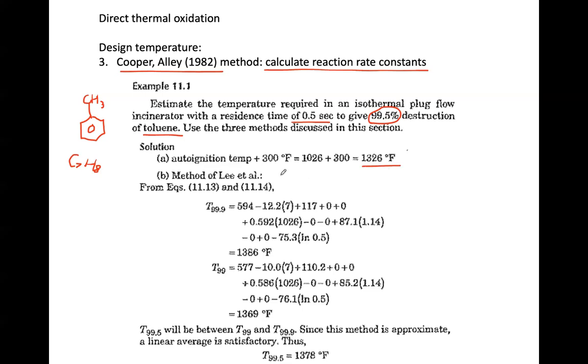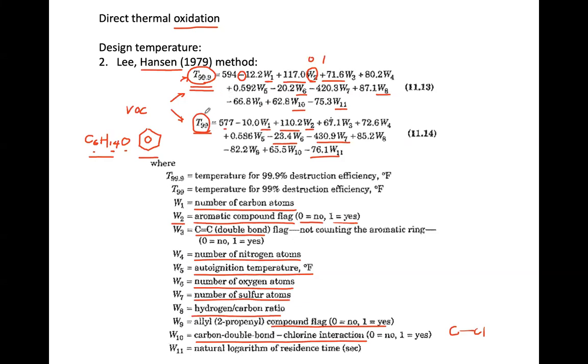For the Ross method, it's simply 300°F above the auto-ignition temperature. Looking up toluene's auto-ignition temperature, which is 1026°F, and adding 300°F gives us 1326°F. That's as simple as that. For the Lee-Hansen method, we know the chemical formula C7H8, so we plug in all the parameter values to find T99.9 and T99.